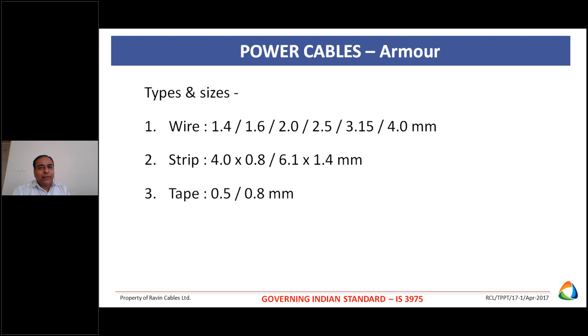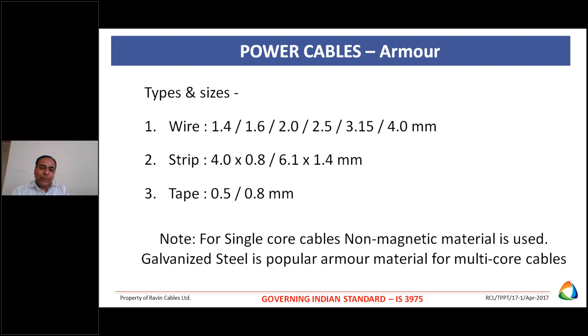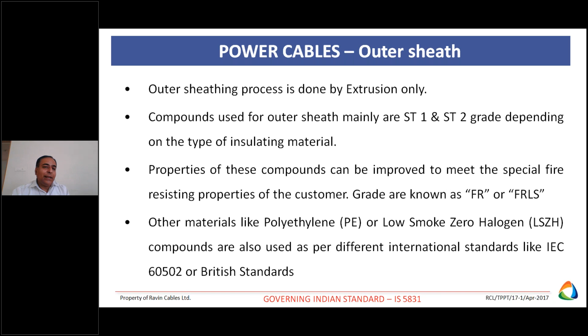Here, very important, especially for single core cables in an AC system, non-magnetic materials are required. Suppose you are using magnetic material, what happens? The cable will be magnetized and this leads to heating. So in case of a single core AC system, non-magnetic materials are required. However, for multi-core cables we are using galvanized steel iron, maybe round armor, maybe strip armor, maybe tapes. To protect the armor, we require sheathing material. That is again made of what? PVC compound with different voltage and temperature grades, with different properties: flame retardant, low smoke, and other types.